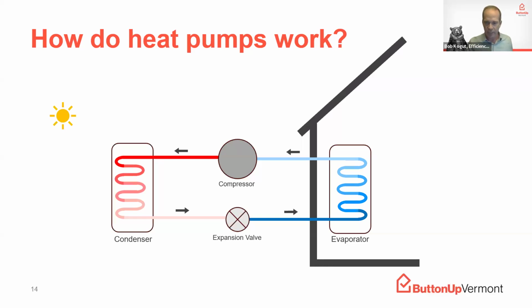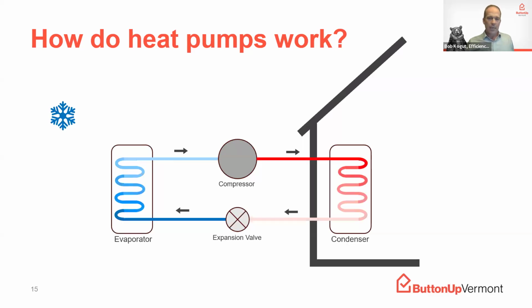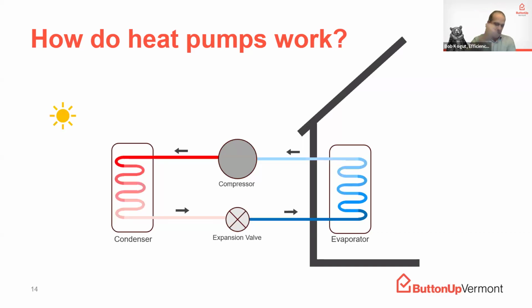This is showing us heat mode here. The interesting thing about a heat pump is, same as a refrigerator or air conditioner in how it operates, it can be run backwards. That's the magic that makes a heat pump different. It has a series of valves that allow you to reverse the fluid flow within the device, running backwards or forwards. In one direction it provides heat, in the other it provides cooling.